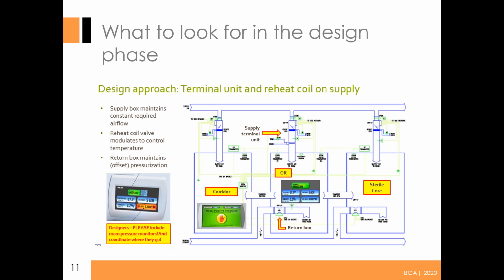And I'll say right here, if you're trying to control the pressure of a room, you must have the control on the supply and the return. You can't just control the pressure on the supply. You have to have them both. And then obviously if there's exhausts involved, that as well. You can't just do one side.